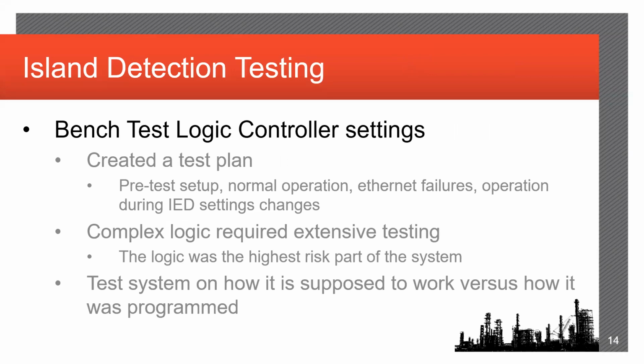So as I was saying earlier, with the level of complication of this logic, it was absolutely crucial that we performed a bench test on the logic controller and its settings. The first step in that process was to create a test plan. The test plan detailed such things as the pre-test setup, just exactly what equipment did we need, how were they going to be connected, IP addresses of various things. It also detailed tests on normal operation. Well, sure, we were going to test how it should normally operate, but then of course we wanted to test all the various failure modes and make sure that the system was operating per the functional specification.